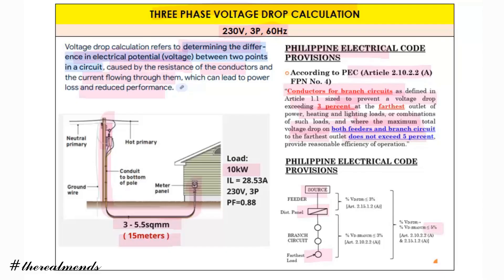So this is critical in your design: from source to distribution panel you can use 2 percent, and then from the branch circuit you have 3 percent, so 3 plus 2 equals 5 percent total. Or you can reverse it — 3 percent on the feeder and 2 percent on the branch circuit.